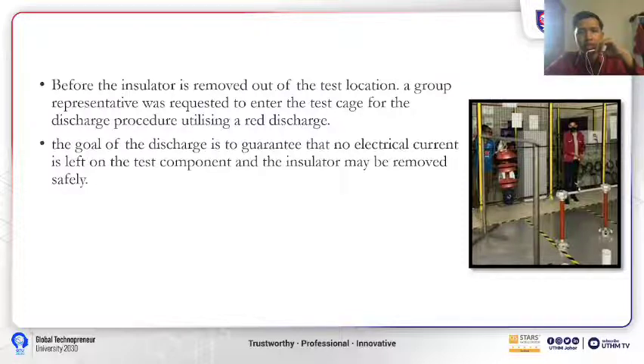Before the insulator is removed from the test location, a group representative was requested to enter the test cage for the discharge procedure, utilizing a red discharge rod. The goal of the discharge is to guarantee that no electrical current is left on the component under test and the insulator may be removed safely.